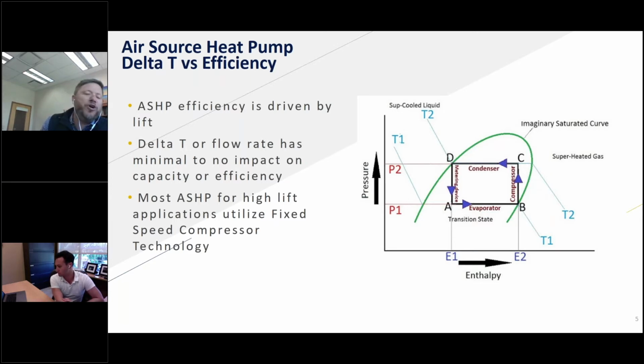So we'll talk more about that, but what that means is I've got a fixed heat exchanger size and a fixed compressor that, based on its lift conditions, is going to deliver a certain amount of capacity at a certain efficiency. That really drives design decisions from a manufacturer's perspective, and those play into how we look at designing a system as a whole. So as I said, we'll talk more about that later.